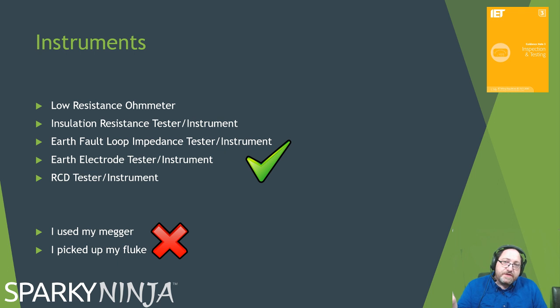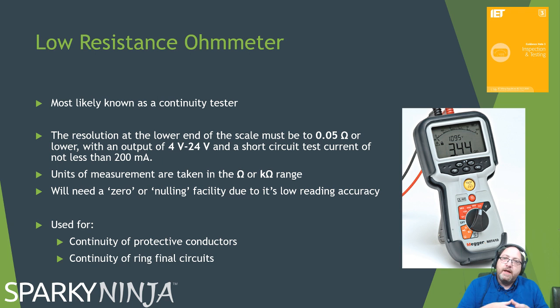So the low resistance ohmmeter, continuity tester. This is key information here. It must read a scale as low as 0.05 ohms. This is so you can verify bonding continuity, for example. And the voltage it applies is between 4 to 24 volts DC on the battery, with a current of no less than 200 milliamps, so you can apply a good continuity measurement.